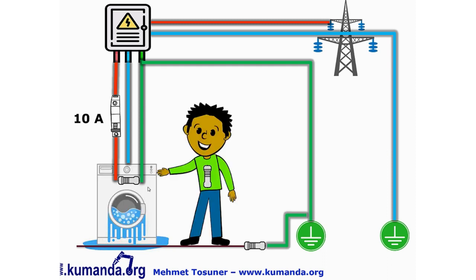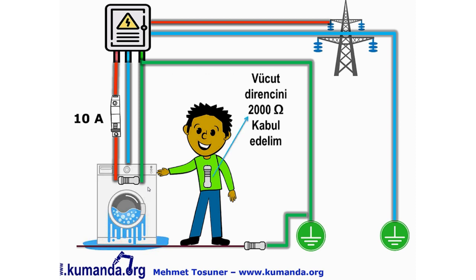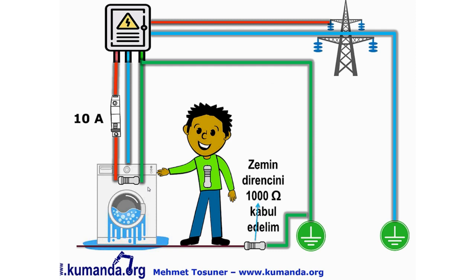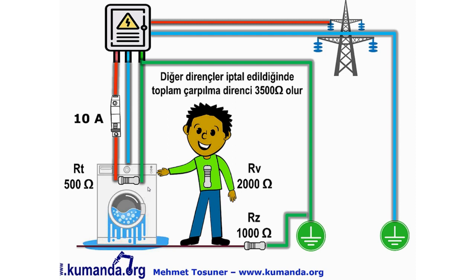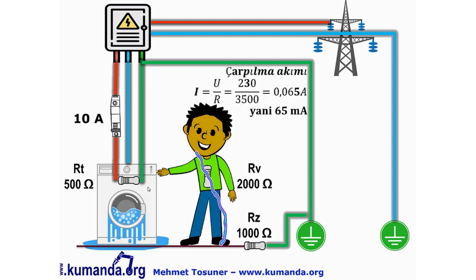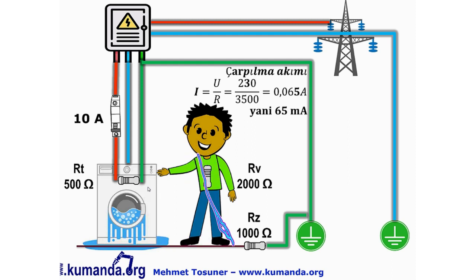İnsan vücudu 1000 ile 3300 Ω arasında dirence sahiptir; 2000 Ω kabul edelim, 1000 Ω zemin direnci olsun. Toplam 3500 Ω dirençte 230/3500 ≈ 65 mA akım kişi üzerinden geçer. 65 mA insan için zarar verici bir akım değeridir.